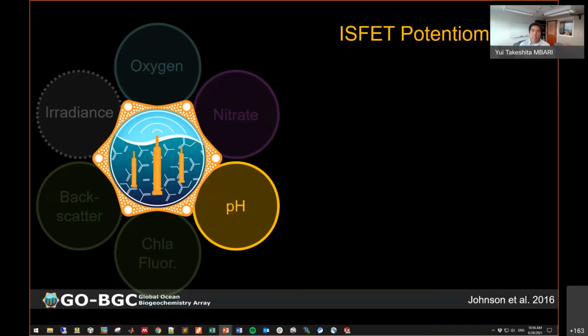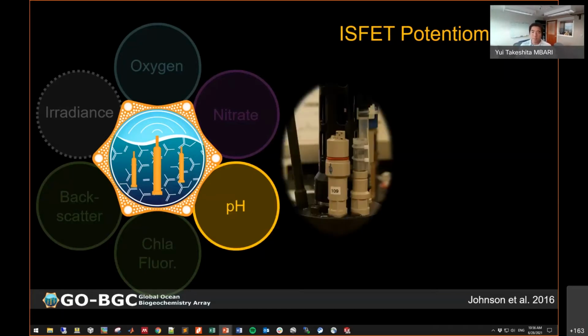pH is measured using the Honeywell ISFET, and it's a potentiometric sensor. This is a picture of the deep sea Durafet. A potentiometric sensor means you measure a voltage between two electrodes. The first electrode is the ISFET, or ion sensitive field effect transistor, manufactured at Honeywell. And this electrode is sensitive to pH.